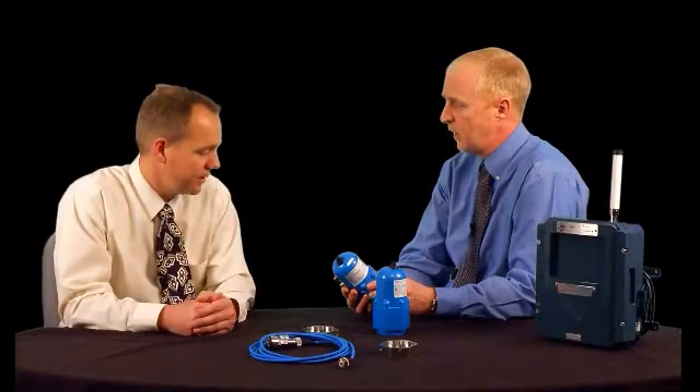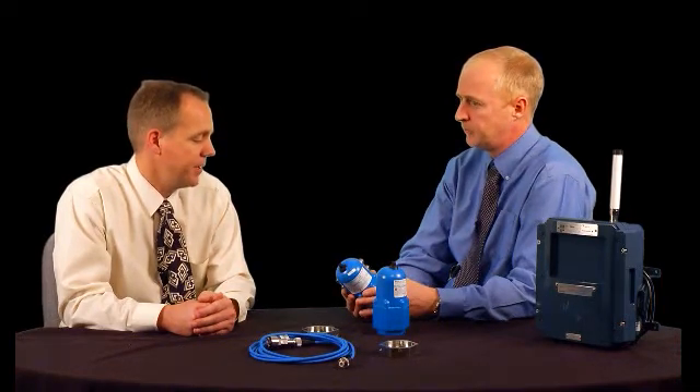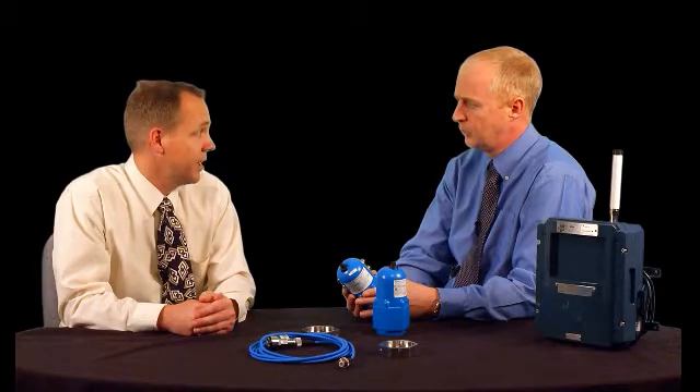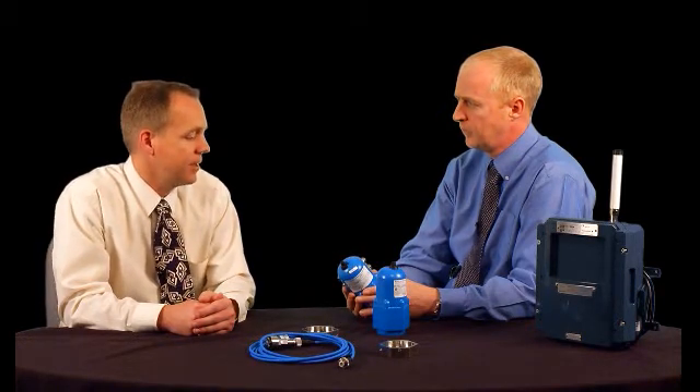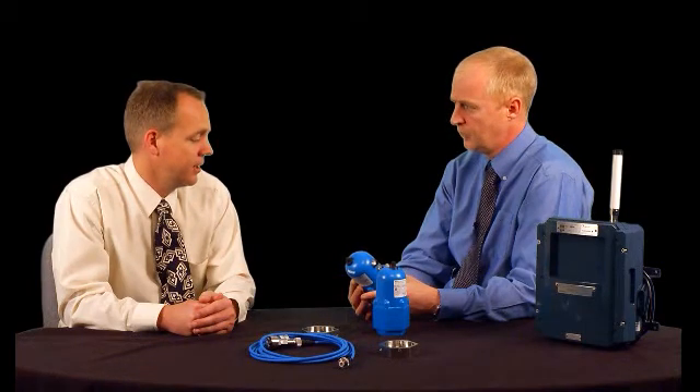We had similar figures confirmed, and it is customizable from System 1 — it can be customized. We call it scanning balance of plant, where we take a set amount of readings and it's not real time. Once the system finds an issue or there's an error, the software will alert you in System 1 when there's high vibration, high temperature, or whatever parameter you've set. The user can set up alarm thresholds based on their own criteria, and once a threshold is exceeded, the software will alarm. At that point the user can decide to investigate further using the data on demand feature, which allows them to request a data collection event immediately rather than wait for the next scheduled interval.